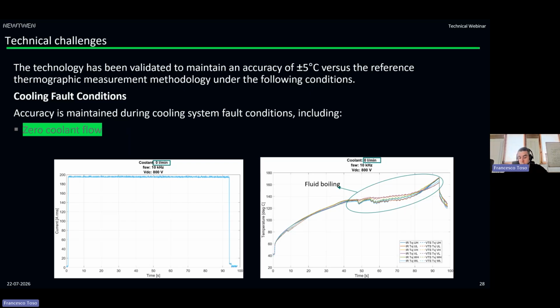One is on the electric pump of the coolant, that is now on fault. And so the coolant has 0 speed. You have 0 liters per minute, but you still have water glycol inside the cooler of your inverter. As you can see, we have almost 200 amp and a dynamic that is completely different from before. Why? Because you have a huge mass of water glycol inside the cooler with a huge heat capacity, and you have to predict this behavior.